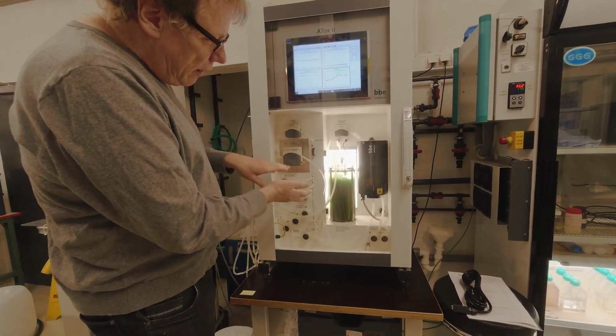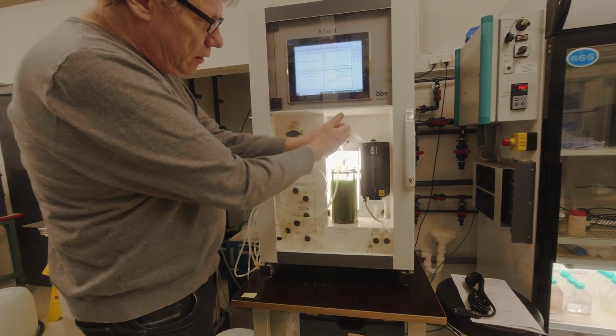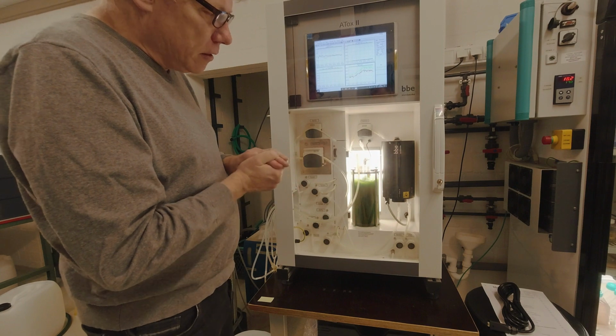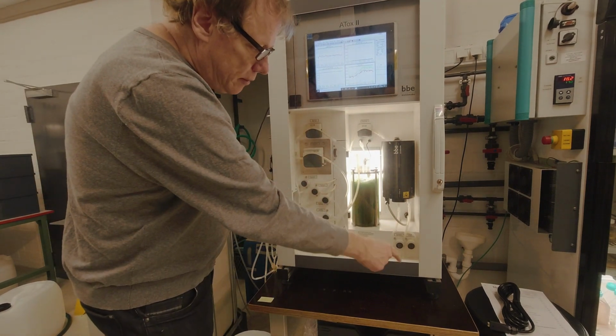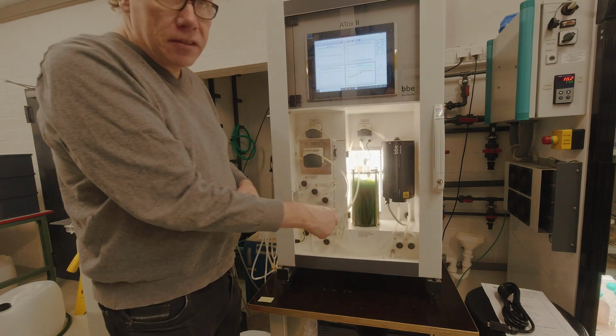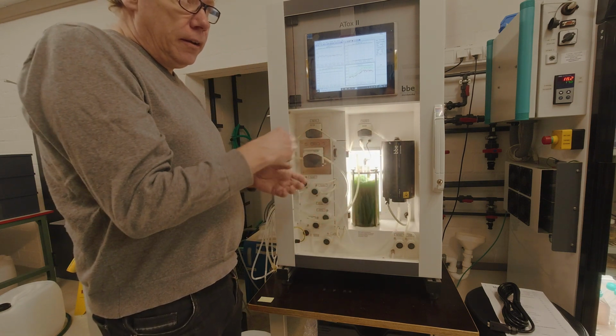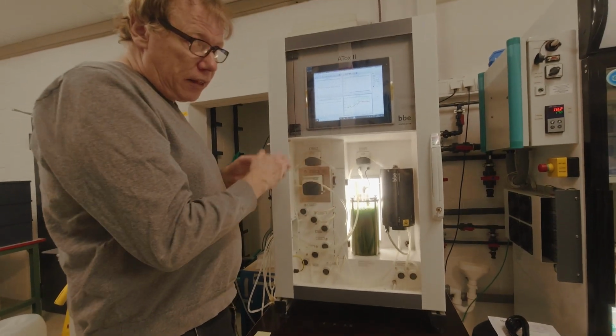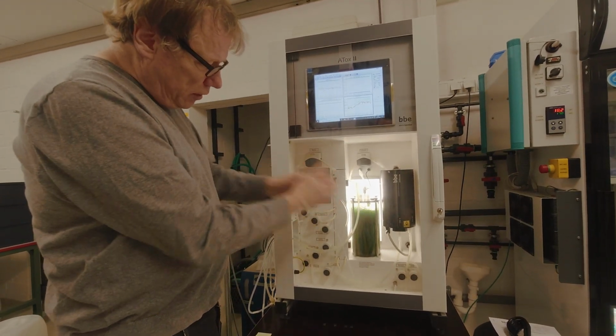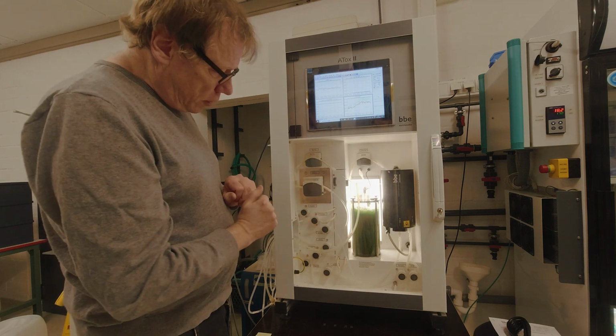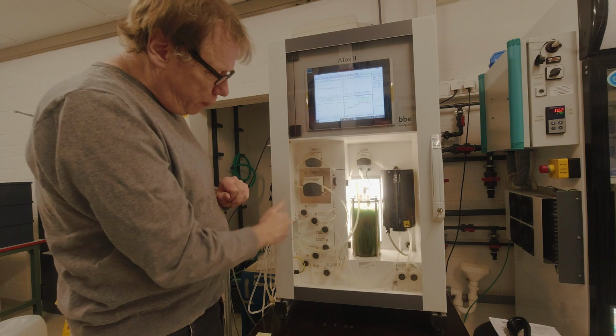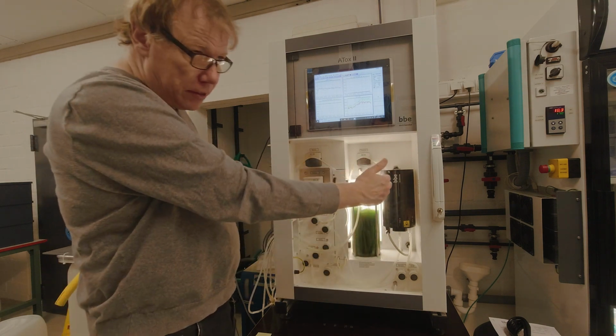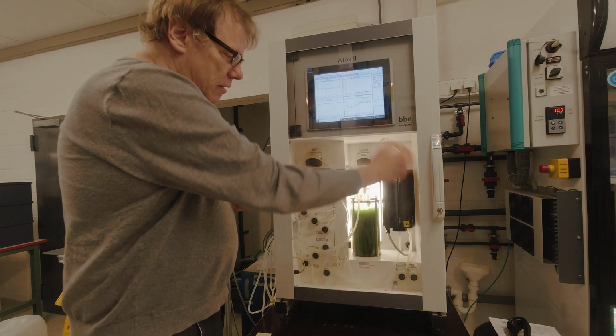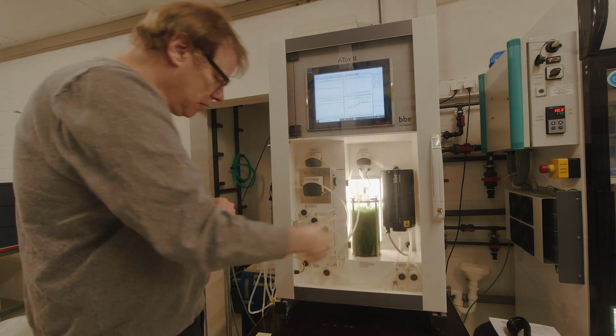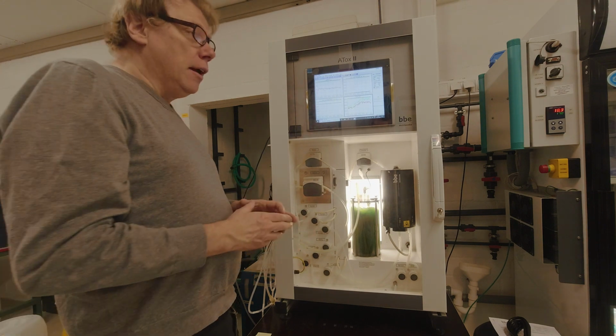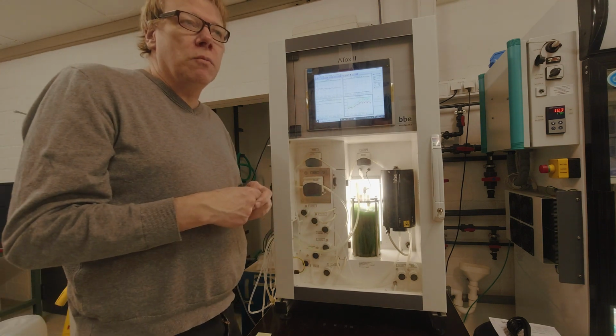By this valve control, we can fill the sensor. Later, after the measurement, we take pressurized air to empty the sensor. So in the measuring cycle, first we fill the water algae mixture into the loops. In the second step, we force this water into the sensor, measure it, and after the measurement, the mixture is pressed into the drain by air, and then we rinse the system with clean water.